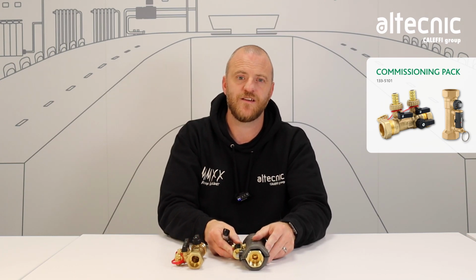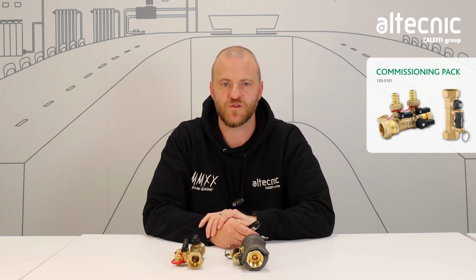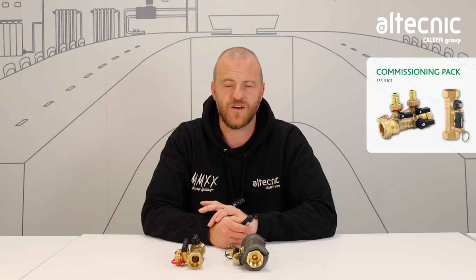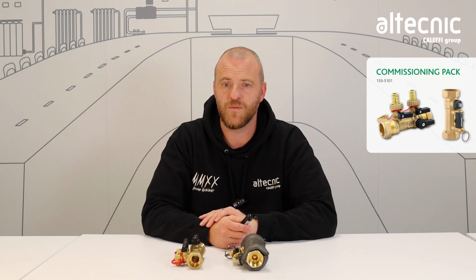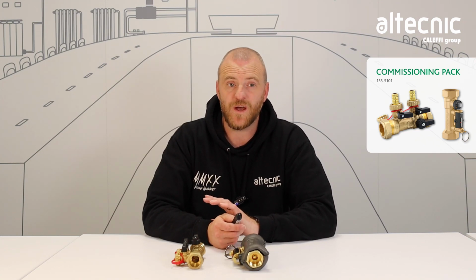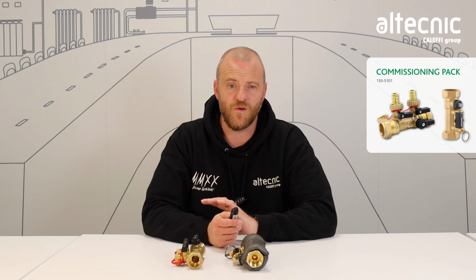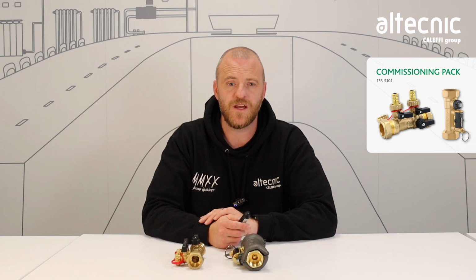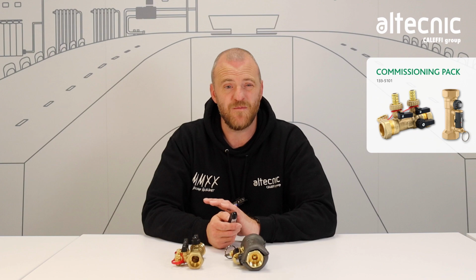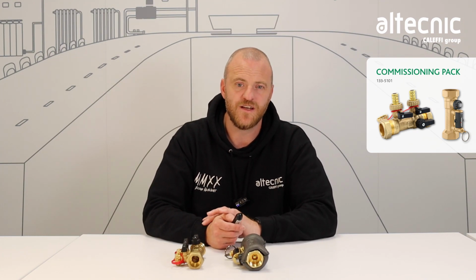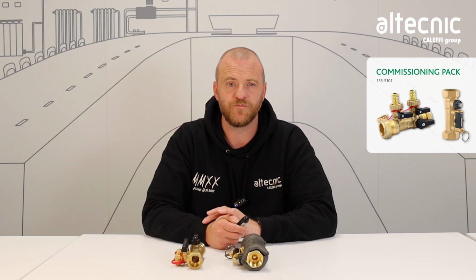So why is the heat pump commissioning kit useful? It's a good question. The efficiency and the combination of the fill and flush valve and the flow meter helps to allow for a quick, efficient setup of the system. Along with easy future maintenance, the engineer-focused design means less joints, less leak paths, and protects the client's investment.